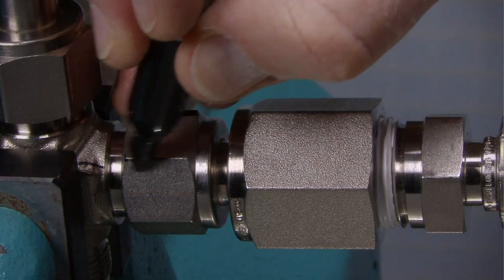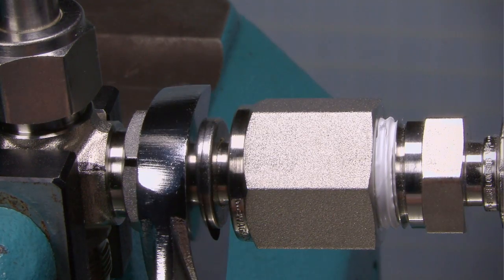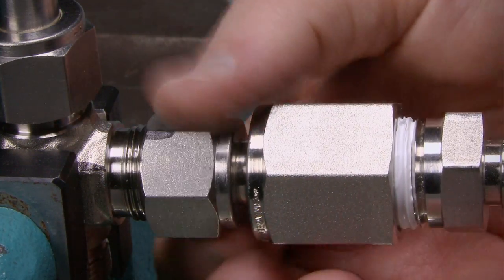Prior to disassembly, mark the tube at the back of the nut. Mark a line along the nut and fitting body flats. Use these marks to ensure that you return the nut to the previously pulled up position.